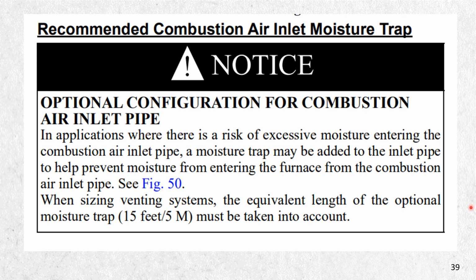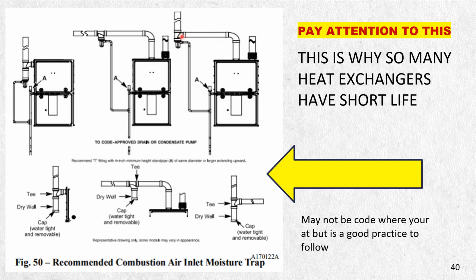Let's say we've got the combustion air, the moisture trap. Like I said earlier, this is something you see in the northern area. I think it's a good idea. We don't practice it here. We don't see it here, but it's a great idea. As you can see right here, when this flue gas is going out and the inducer motor's on, and the air's coming out of the combustion, when that blower motor stops, all this turns back down to a liquid, and it's going to come down and go right here and flow right out the drain instead of running back into the furnace. So there's a couple of ways of doing it.